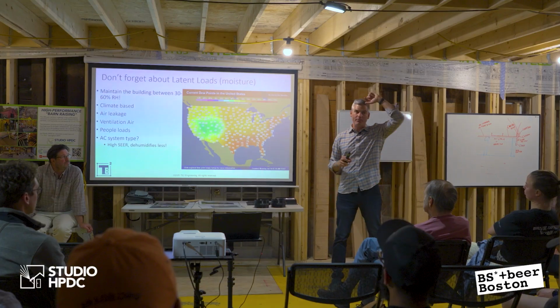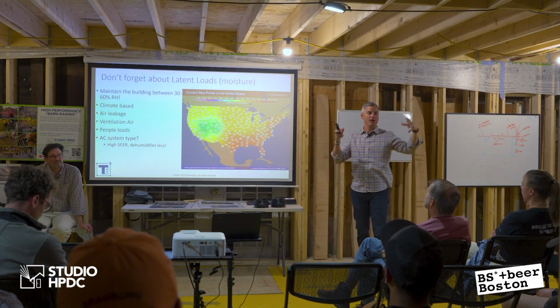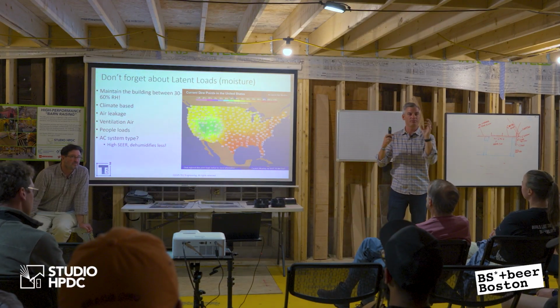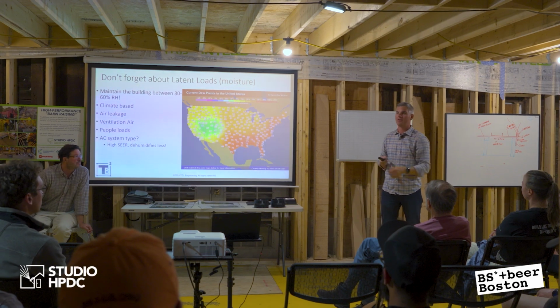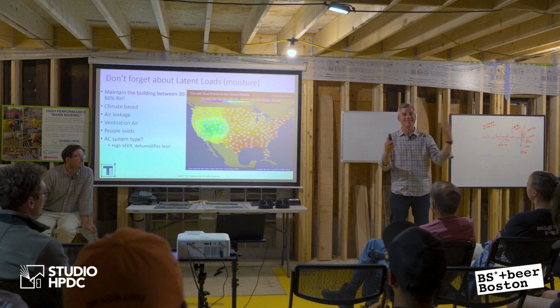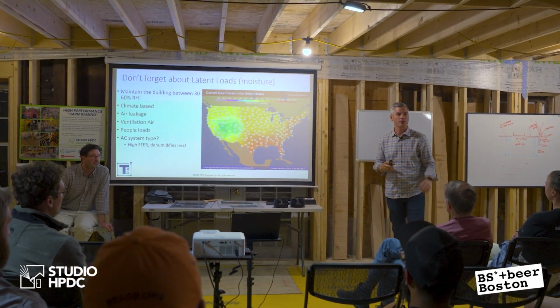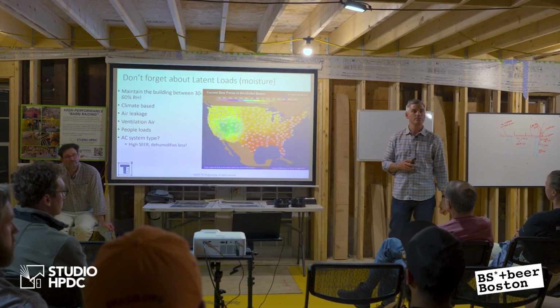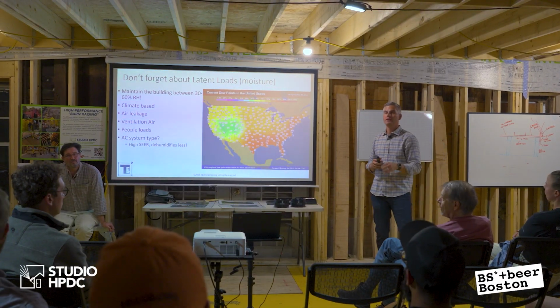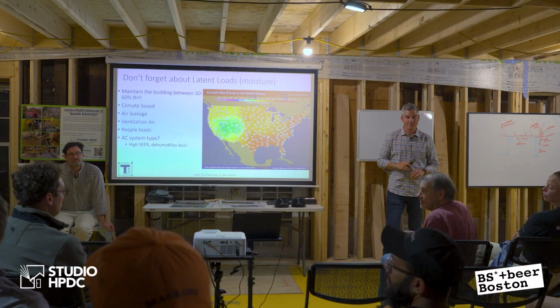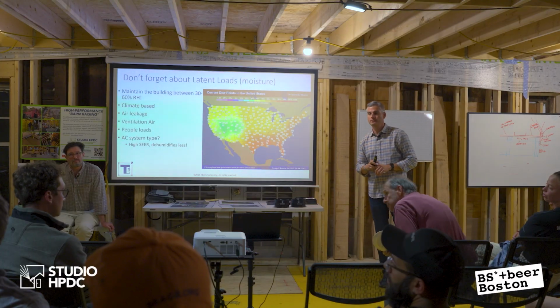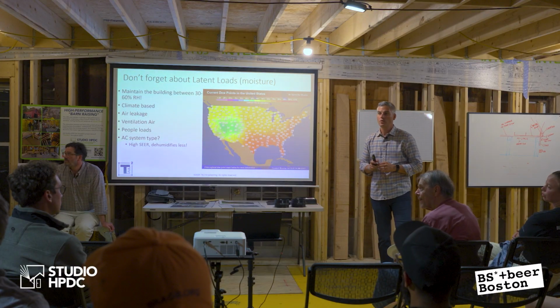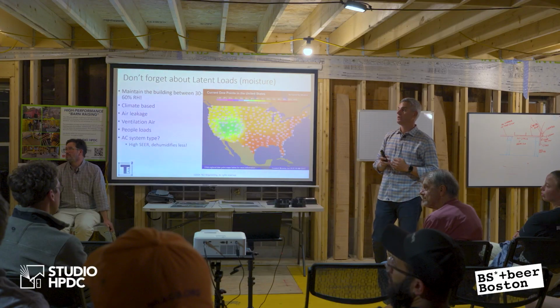I'm not sure which topic or segment you watched, because we've done mold inside the building due to lack of dehumidification. We've also talked about mold inside the air handler cabinet. But in the mini split, you have coils and mold, because of where the coil is and where the air is coming in with those mini splits. It's because the fan's on the cold side of the coil.